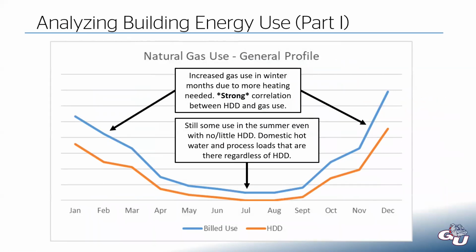And that's not what you should see if you're running things efficiently, unless you truly have a year-round gas load that is truly needed. But in that case that I'm thinking of, it was a convention center. And what had happened is their HVAC controls were so messed up that they were just burning gas year-round. Didn't matter how warm or hot it was, essentially a flat line from January to December. And I can look at that and say, there's a lot of opportunity there. And sure enough, there was.